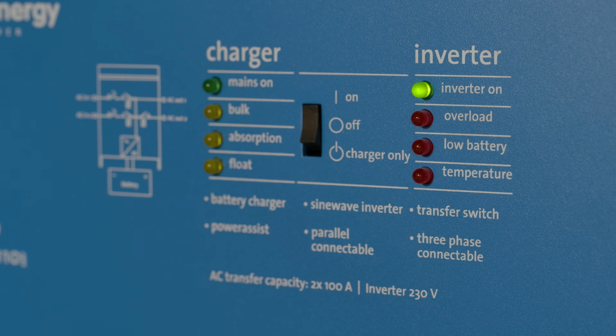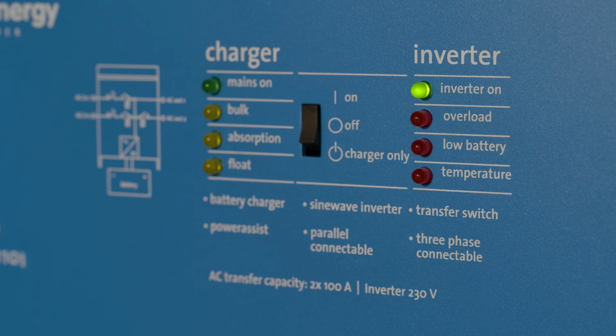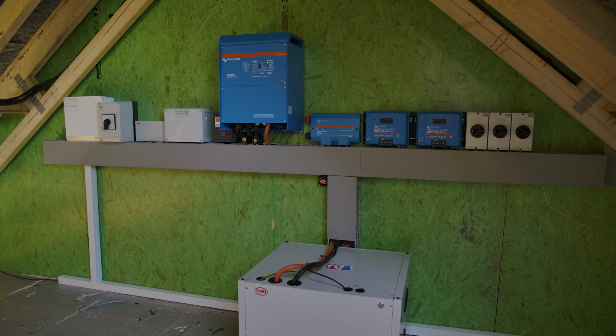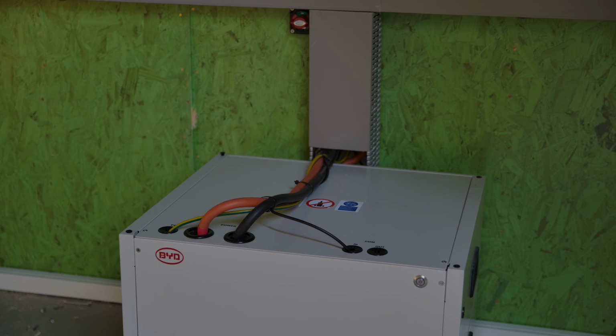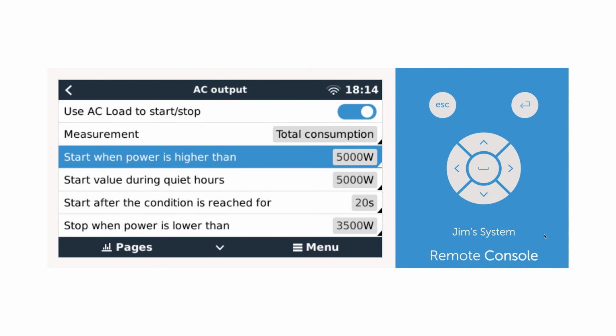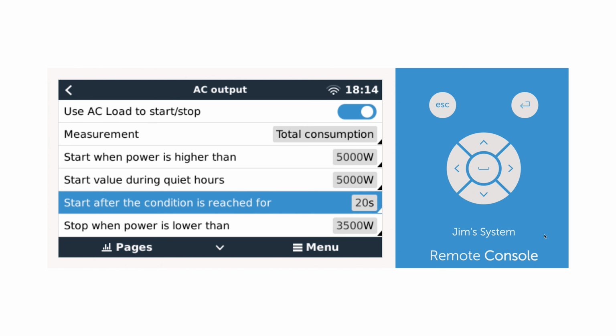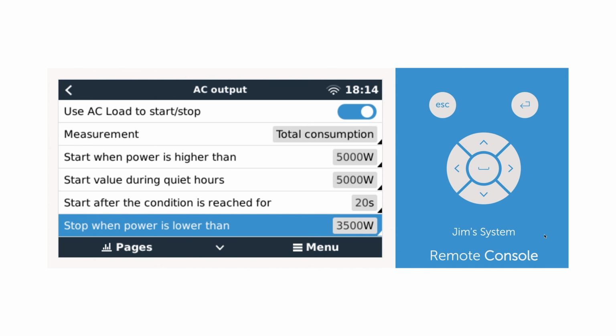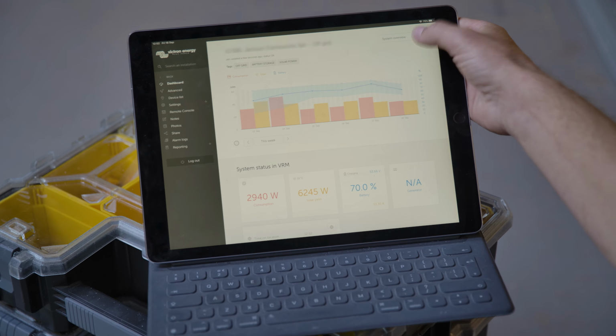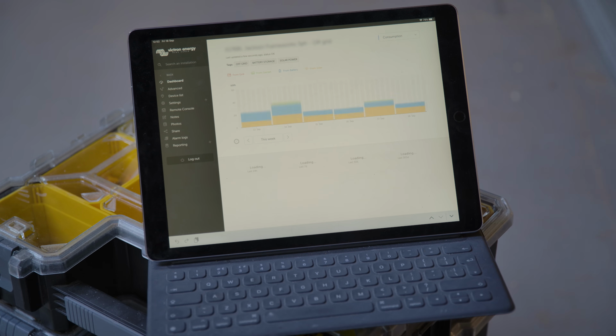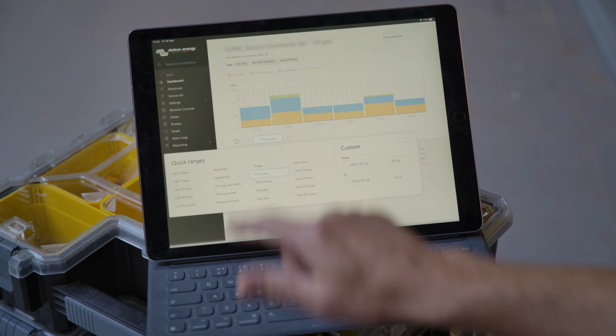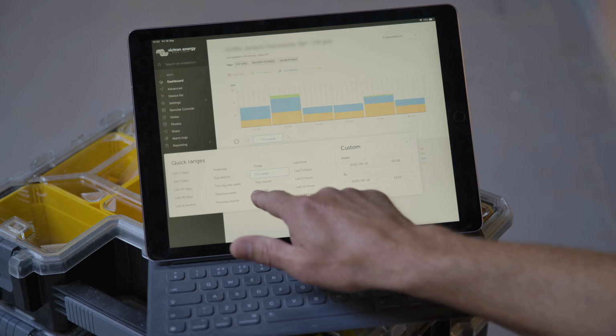In this install, the generator will turn on and power assist the Quattro should there be an AC power requirement within the house of more than 5,000 watts for over 20 seconds. Once the AC power load is lower than 3,500 watts, the generator will be stopped. All this data is fed up to the VRM portal, and with the power of know-how, Ian can monitor and look after Jim's system from afar.